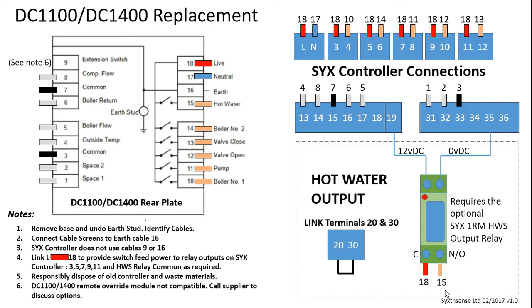The earth stud on the rear of the product will be hosting the screens for the sensors. Undo that. Keep the sensor screens intact. These will be connected to an earthing point once all of the other wiring changes have been made. We'll maintain a connection to the earth cable, which is connected into terminal 16. You're going to have to find a good clamping arrangement to keep those screens to the cable inside terminal 16. Also bond it to the rear of the cabinet as an appropriate location, but they do not connect into the SYX controller at any stage.